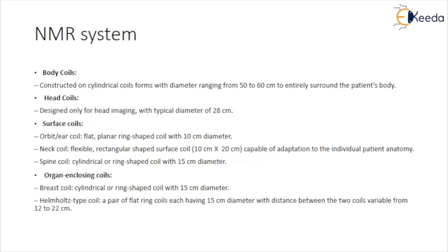Neck coil: flexible, rectangular-shaped surface coil capable of adaptation to the individual patient anatomy. Spine coil: cylindrical or ring-shaped coil with 15 cm diameter. Organ-enclosing coils — breast coil: cylindrical or ring-shaped coil with a 15 cm diameter. Helmholtz type coil: a pair of flat ring coils each having 15 cm diameter with the distance between the two coils variable from 12 to 22 cm.